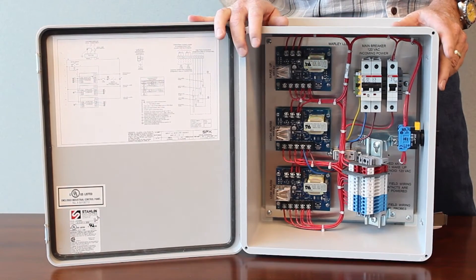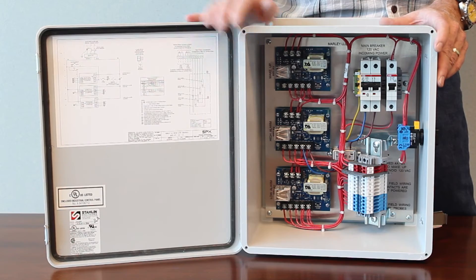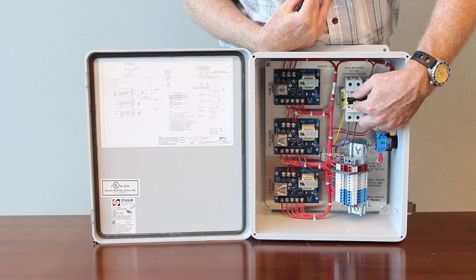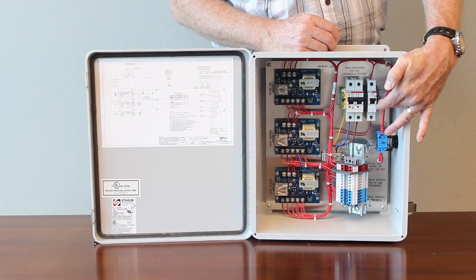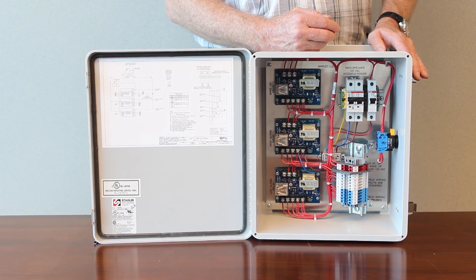This is a 120 volt single phase 60 and 50 cycle control panel. Inside here we have a main circuit breaker that is rated at 6 amps. So this panel requires 6 amps of power. There's also another circuit breaker in here and we'll talk about that a little bit later which feeds power to your solenoid.